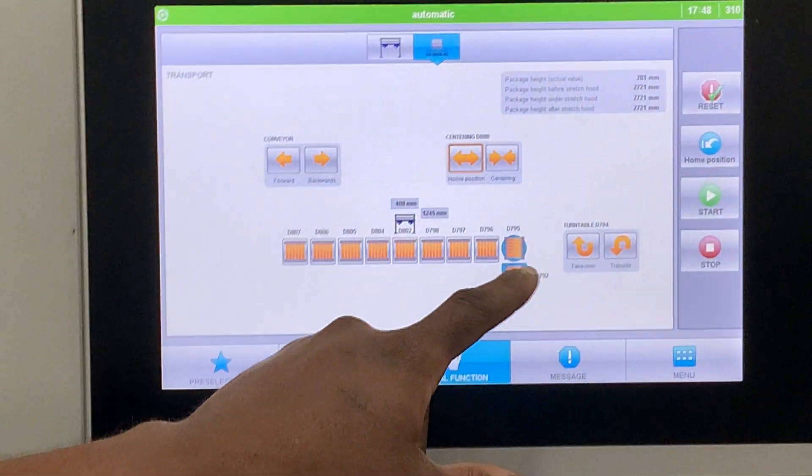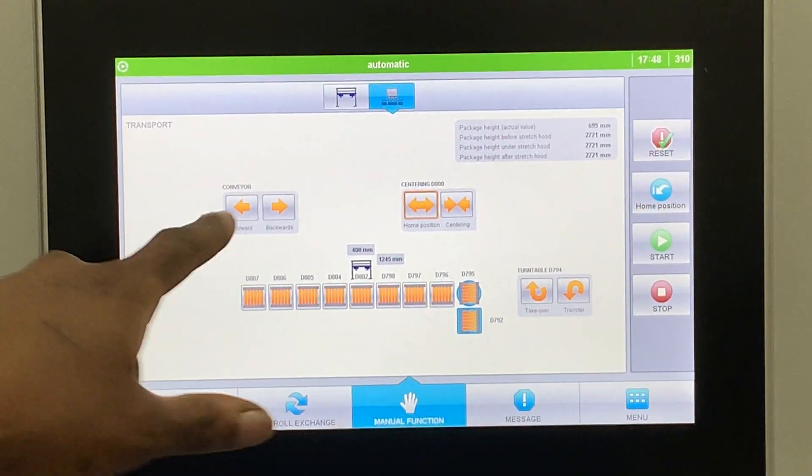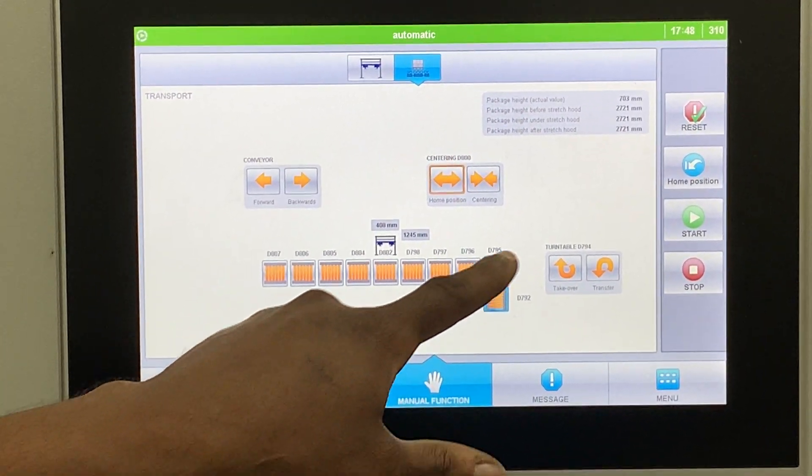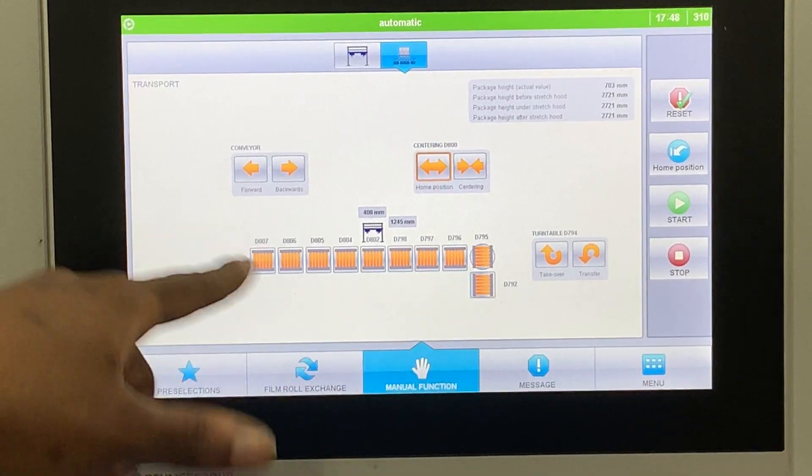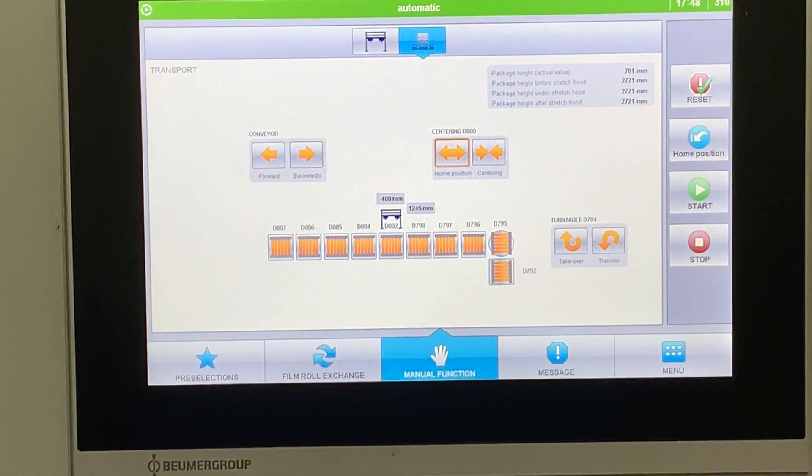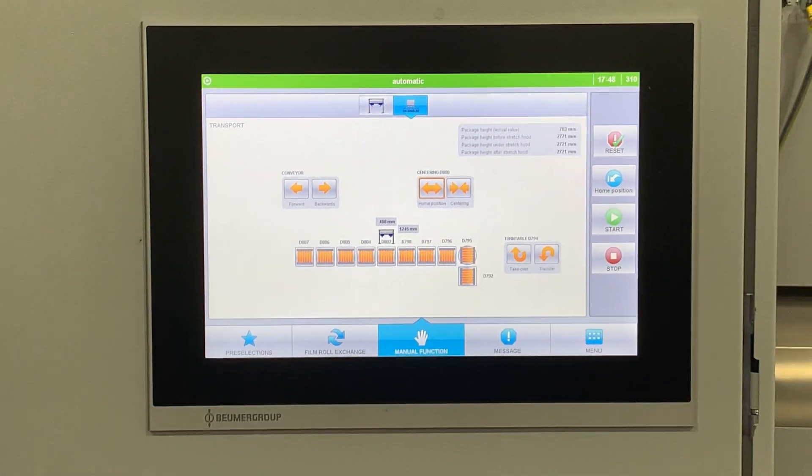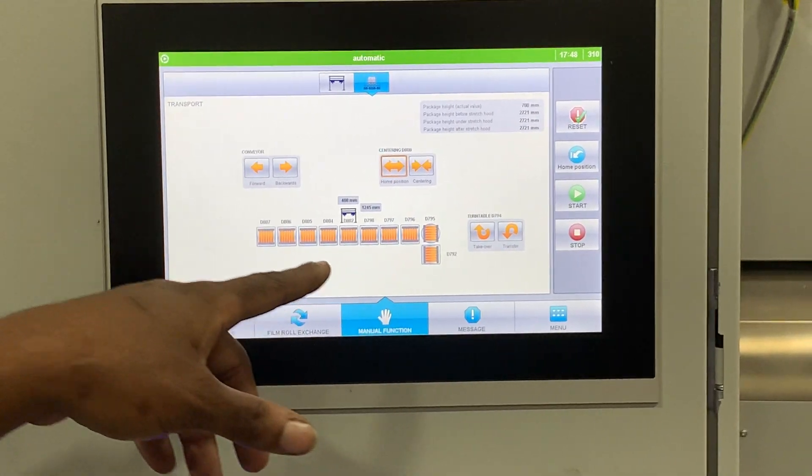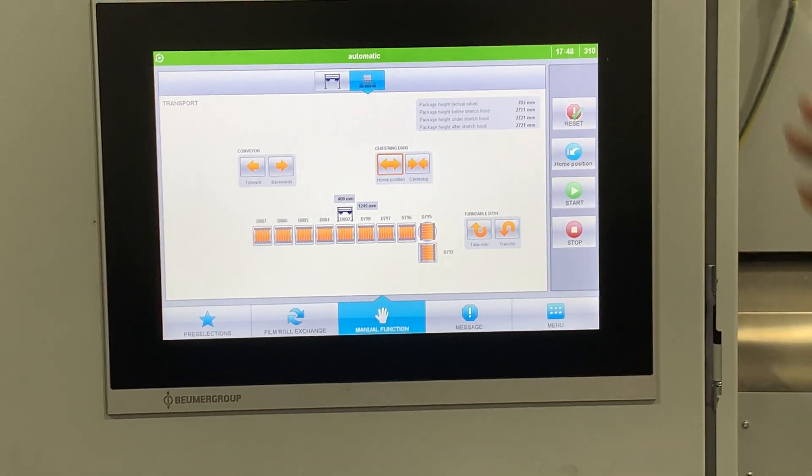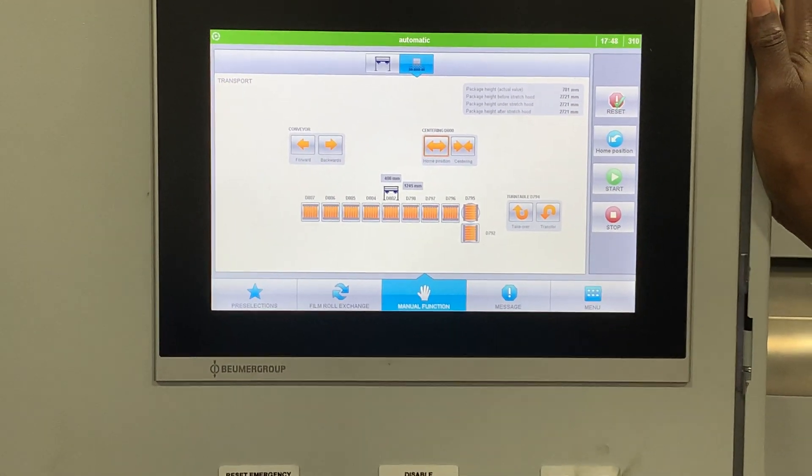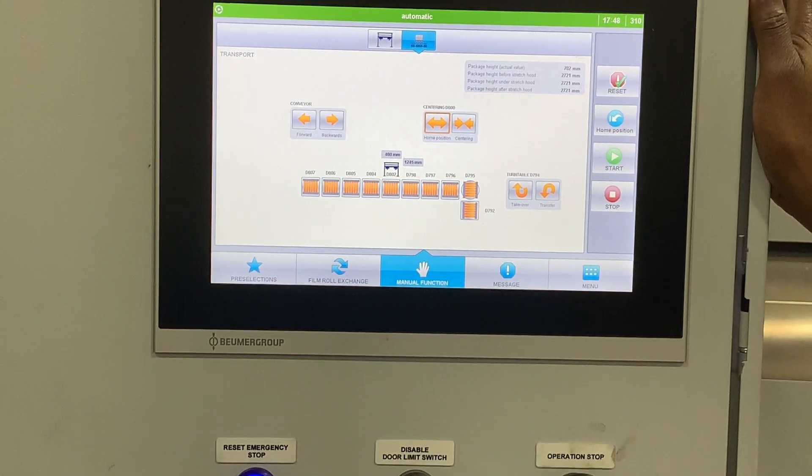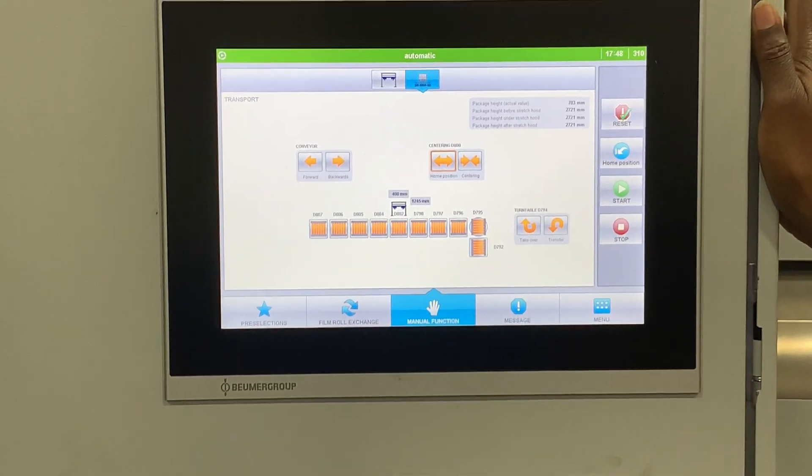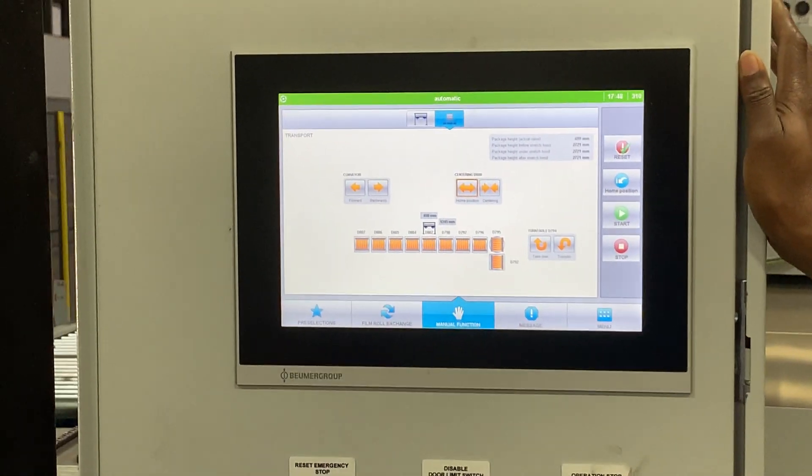If we get a pallet in between two photo eyes, it don't know where it is. That's one of the problems we always got with the transfer of pallets. They use timers, we use memory. We say I remember I was doing this. So you'd have to go in there and manually push the pallet. That's the only way.